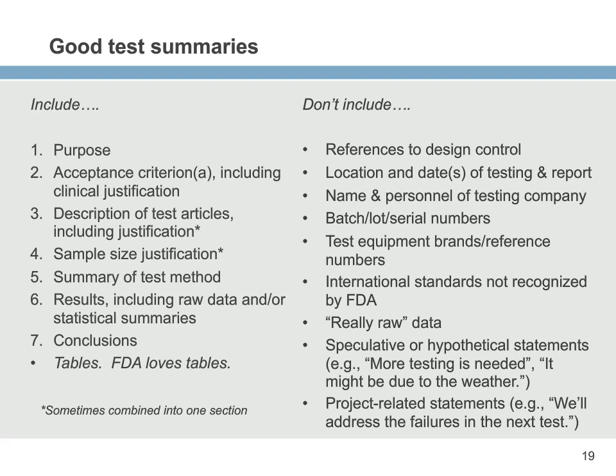So same thing, batch, lot, serial numbers, not really critical. It doesn't mean a whole lot to FDA if you introduce a test by saying we tested lots number XYZ1, XYZ5, and ABC10. They have no reference. They don't know what that means. Important for traceability, but not for a test summary. So a lot of times I'll just say, hey, lot 1, lot 2, lot 3. And then refer them back to the test report if need be. Same thing with test equipment. It's not really important to have the brands there. If you're dealing with FDA, telling them that it complies with an international standard that they haven't recognized is not relevant, and might even backfire. And then there's raw data. You generally try to avoid giving them reams of paperwork that's hard to interpret in a test summary. You may have to send it in, for instance, with an animal test. They usually require all the raw data, but you don't need to do that in your summary.